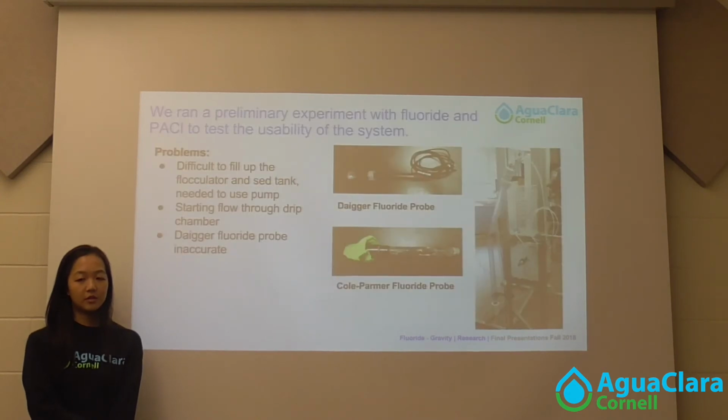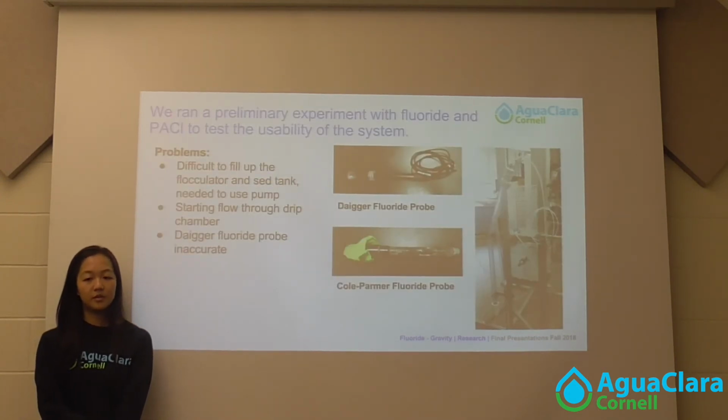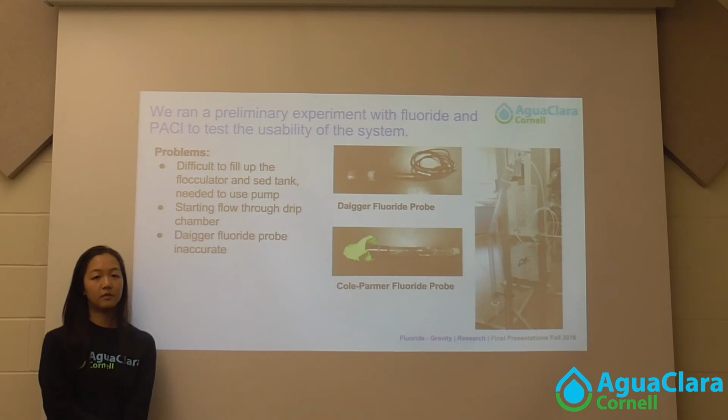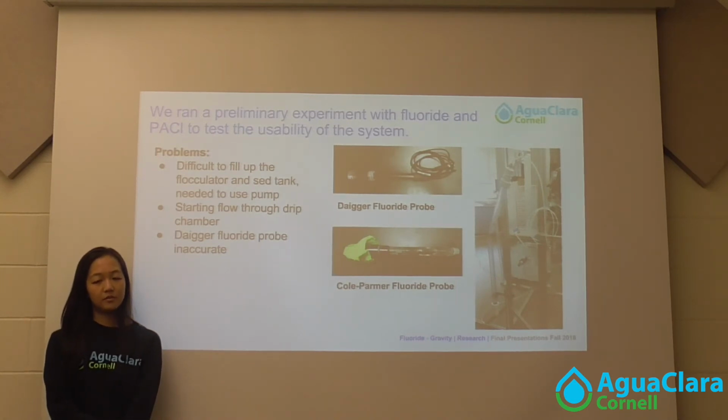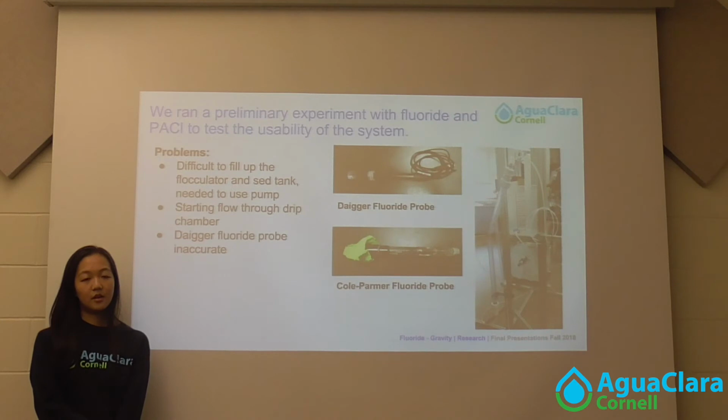The other issue we ran into is that there were air bubbles in the microbore tubing, which prevented flow out of the drip chamber. So in order to account for that, we had to take the air bubbles out.